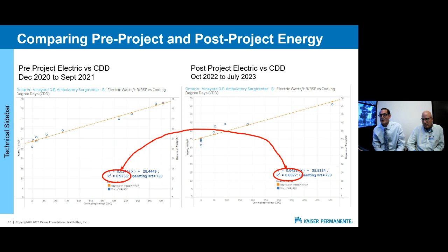The third thing we look at is the accuracy of the model, the R-squared of the linear regression. In this case, the pre-project model is significantly better than the post-project model. On the left, we see an R-squared of 0.97, meaning the variance in cooling degree days can explain 97% of the variance in the electrical data. That's quite good. A lot of what we'll see here is less than 80%.